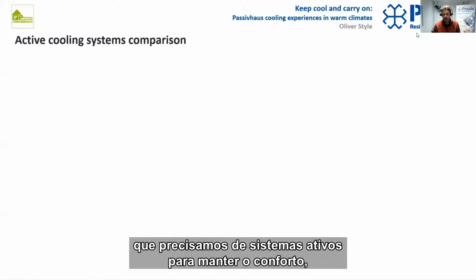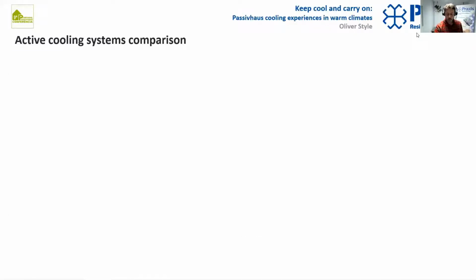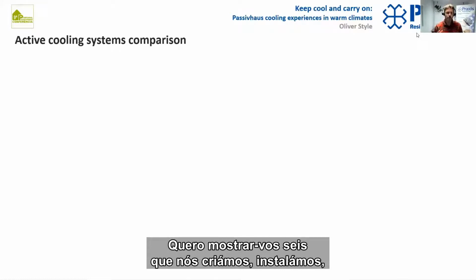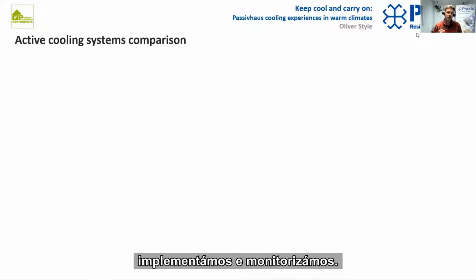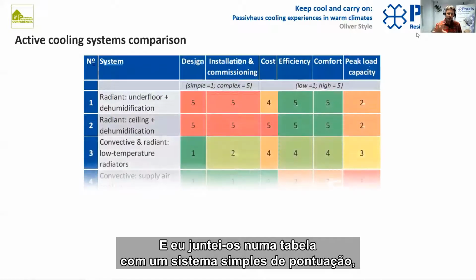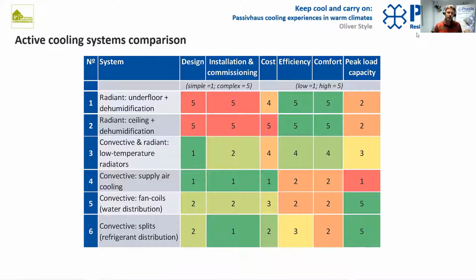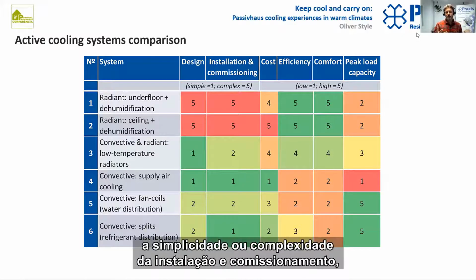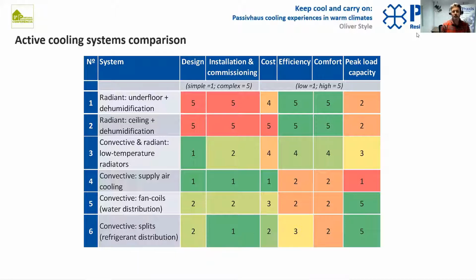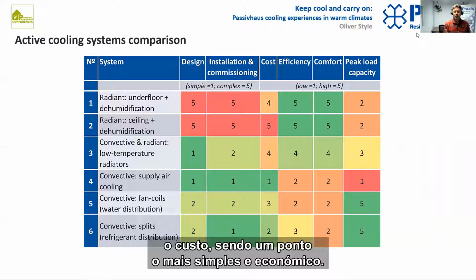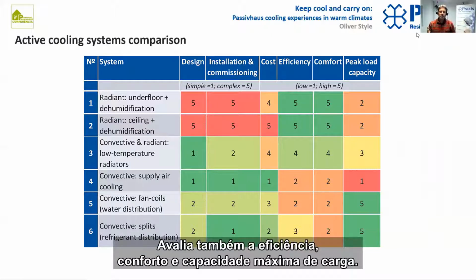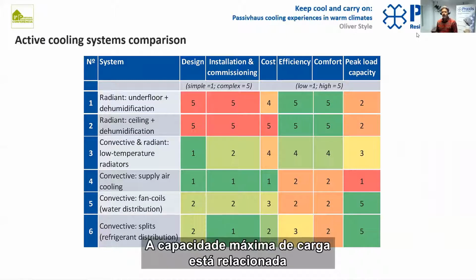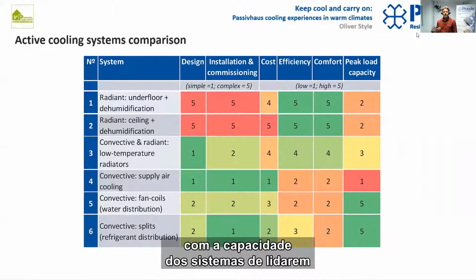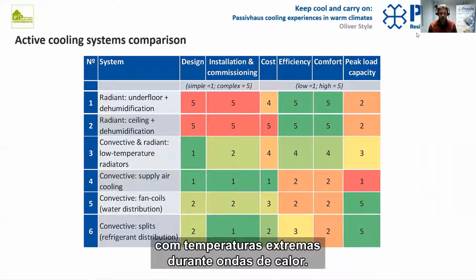So once we've exhausted all of our passive cooling strategies and we've worked out that we really need some active systems to maintain comfort, what are the alternatives? Of course, there are multiple different systems. What I wanted to present here are 6 different ones which we designed, installed, implemented, and monitored. And I've put them together in this table, which just with a quick and simple point scoring system looks at design, installation, and commissioning simplicity or complexity and cost. One being the most simple or the most economical, and then looking at efficiency, comfort, and peak load capacity. So peak load capacity is how capable are these kind of systems at dealing with extreme temperatures during heat waves.